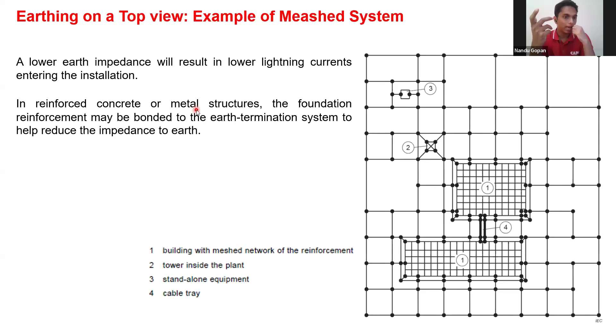The standard has put a particular point in the 62305 part 4 series. The earth termination system can be improved by installing an additional earth point close to the connection point of the power utility. They have explained and put this clause on earthing systems.